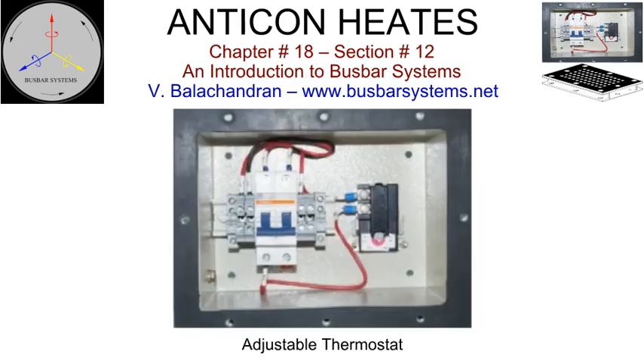Thermostats trigger heaters when the temperature falls below a set point. Hygrostats turn the heaters on when humidity rises above a given threshold. Hygrotherms do both. Using hygrostats to control heaters is considered more energy efficient but more expensive. The use of an adjustable thermostat is an invitation for the user to reduce the thermostat setting to save energy, in the process, significantly increasing the likelihood of condensation.